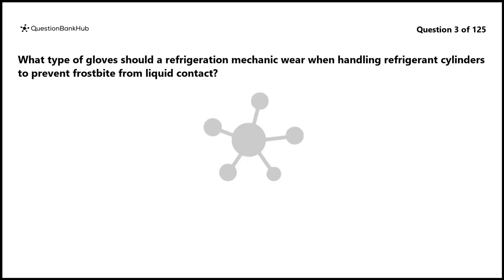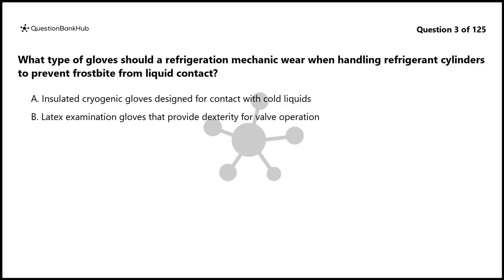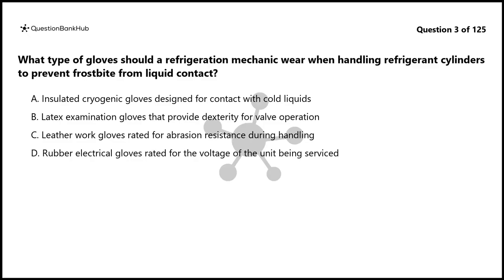Question 3. What type of gloves should a refrigeration mechanic wear when handling refrigerant cylinders to prevent frostbite from liquid contact? A. Insulated cryogenic gloves designed for contact with cold liquids. B. Latex examination gloves that provide dexterity for valve operation. C. Leather work gloves rated for abrasion resistance during handling. D. Rubber electrical gloves rated for the voltage of the unit being serviced.